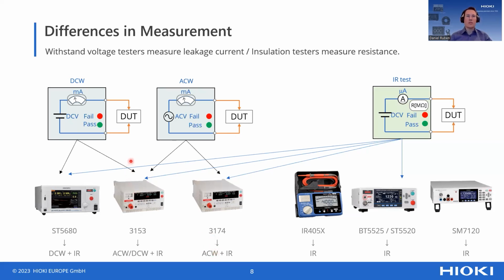The circuitry is quite simple: we apply a DC or AC voltage to the device under test, and out of that we sense the current. The customer is mainly interested in understanding the leakage current, to see whether the insulation is already bad from the assembly process, avoiding problems and, in the worst case, any electrical shock caused by leakage currents. Now we compare this against an insulation resistance tester - in this case for battery, it would be the BT5525.